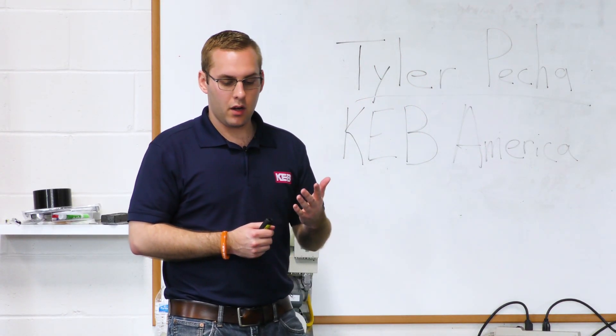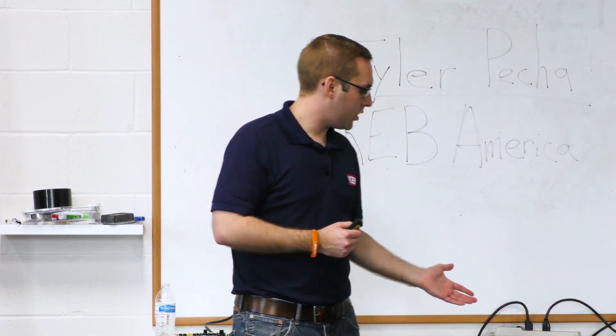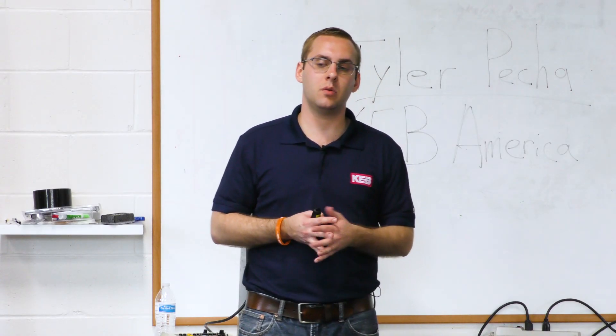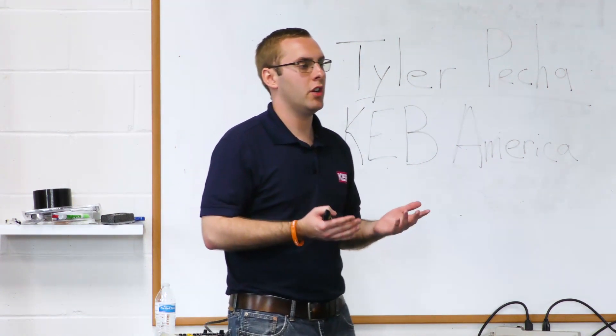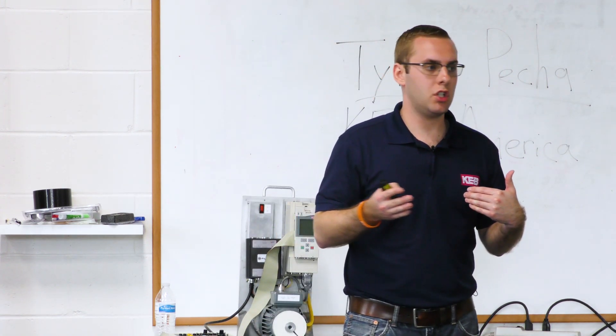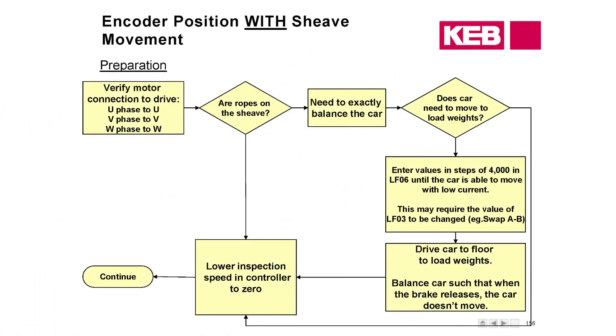Depending on the motor type, some motors — because of how they're designed and the materials used — will feature higher inductance. With higher inductance, the drive has a harder time measuring the encoder position in the background and may give an error saying the counts were varying too much and it could not calculate the position. In that case it might say try another method. That other method is the pole learn, which does the same as the SPI but needs to be done with no ropes on the sheave or a balanced car.